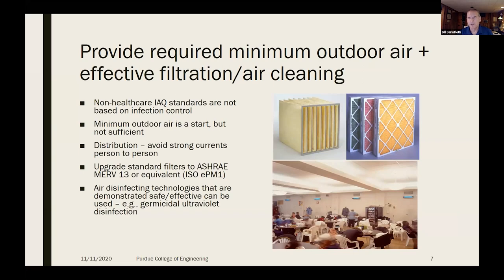And to ventilation, we need to add filters that actually work on those small particles that Dr. Boor was talking about. So we upgrade from low MERV ratings, the ASHRAE standard 52.2 system, MERV 6 or 8, to MERV 13, or equivalently ISO ePM1, which will control the micron and submicron particles. And we can enhance that further with air disinfection technologies, ultraviolet and others that are available.